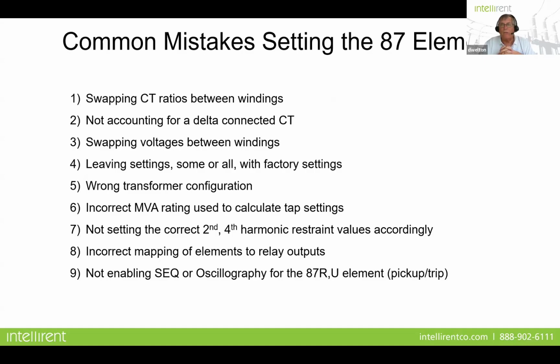Now, what common mistakes do we see when we're setting the 87 element? Well, a couple of things you want to look for. Number one is swapping out CT ratios between the windings, and that's easy to do if you're not carefully looking at the nameplate data. So that's one thing I've seen. The other is not accounting for a delta connected CT. A delta connected CT is sometimes there when you've gone from, let's say, an electromechanical relay to a digital relay and you don't want to add another CT to the system. So you just have to account for the fact that that's a delta connected CT. Well, what does that do to your calculation for the tap setting? It's going to incorporate the square root of 3 factor into the tap setting calculation. So you have to make sure the relay is set to accommodate a delta connected CT.